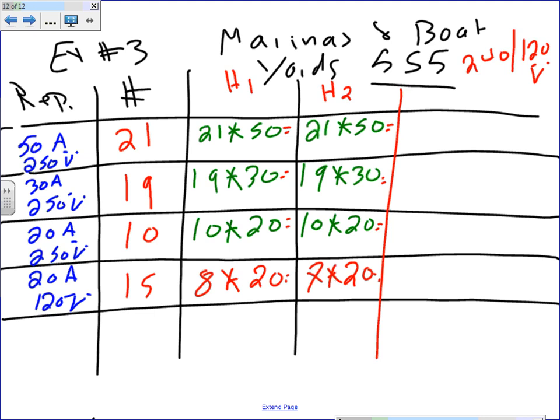1,980 amps here. Anybody second? Second, third, fourth, okay. The second leg? 1,960. Any second, third? Okay. Can you guys see the legs are not completely balanced, but they're balanced enough because Oladipo decided to have an extra receptacle on one leg.